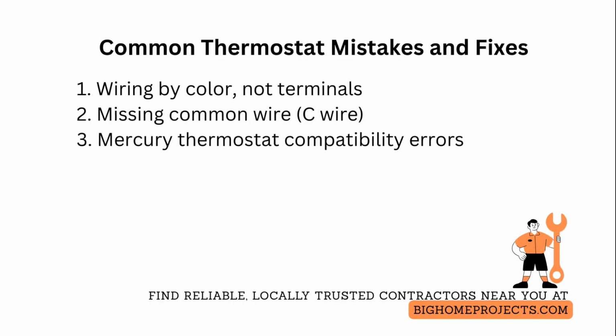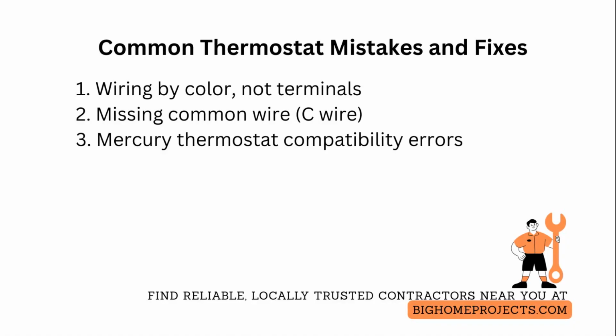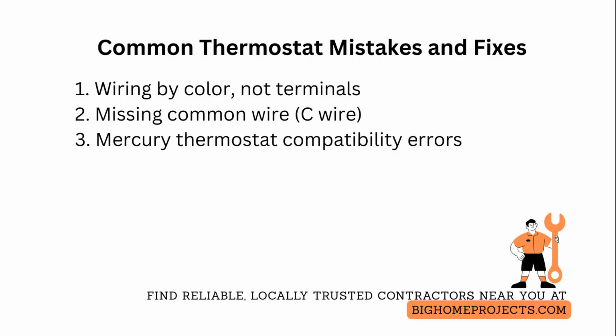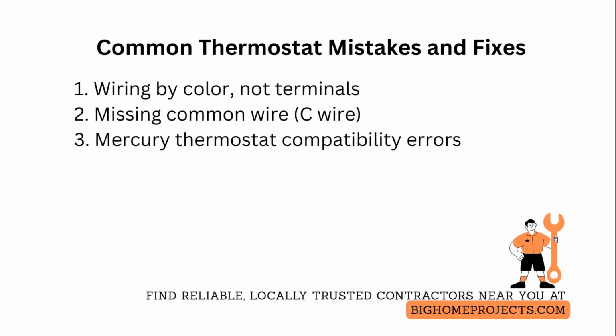One of the most common thermostat mistakes is thermostat wiring errors, where homeowners connect wires by color instead of terminal letter, causing the fan to run continuously or the system to lock out. Fix by labeling wires, matching terminal letters, and confirming with a voltmeter.